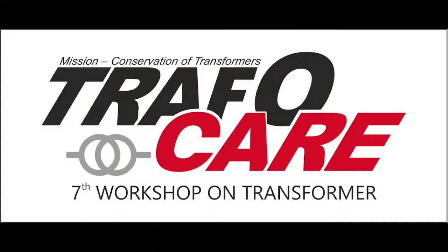Recently we got one incident where we did oil filtration using an external tank and filled up the oil. If you are trying to remove moisture from the transformer, that's a different story - you drain out the oil, take it separately, and do the vacuum process. That's a different process, but if you're doing routine filtration through the tank, it's okay.